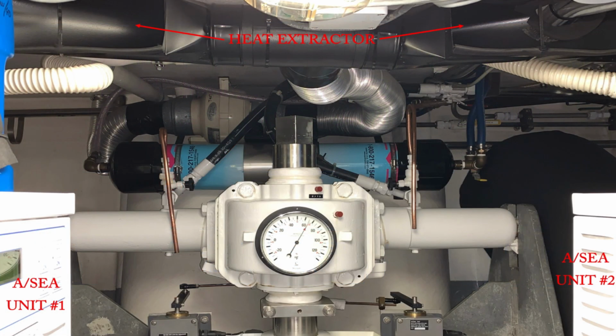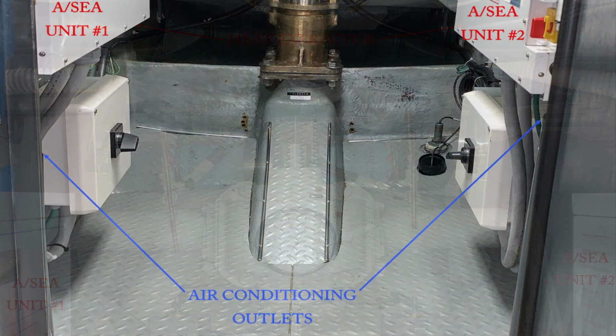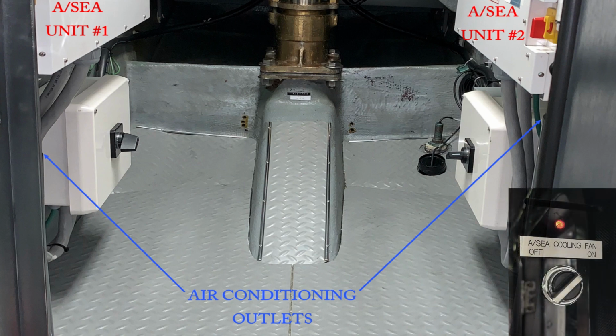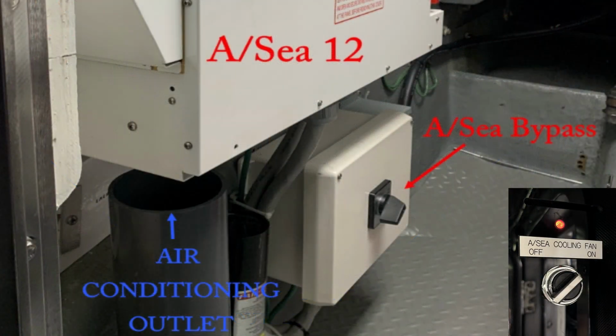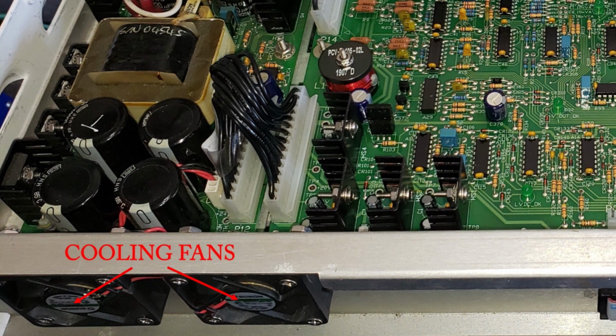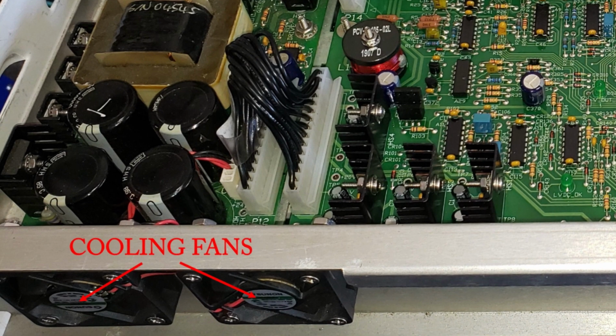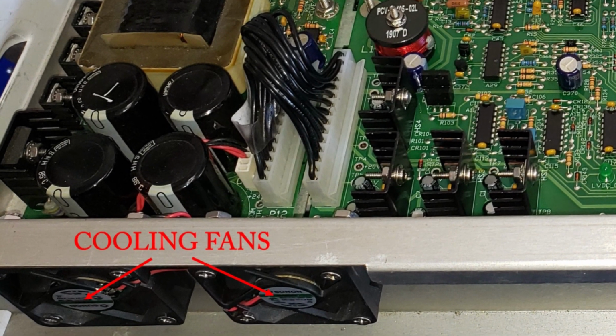Here are two other points worth raising. First, frequency drives need to be installed in a well-ventilated area, and/or you need the ability to climate control the space. They should not be located in areas susceptible to large amounts of dust and debris, as their internal cooling fans will vacuum up this material and deposit it on the control circuitry.